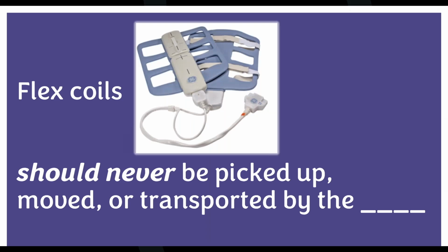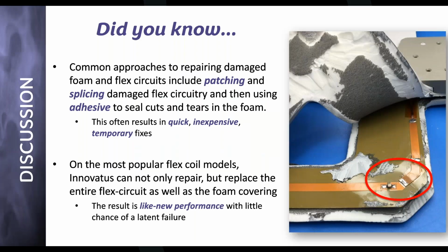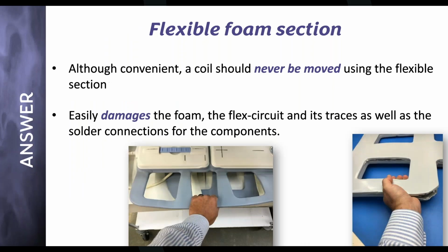Flex coils should never be picked up or moved by the... Anybody else? Patient. Well, no, you shouldn't be picking up your patients anyway, unless you're really strong. So, no, they should never be picked up by the foam section. Even though they're convenient and there seem to be nice handholds on them. Yeah, it looks like a handle. It is not. Inside there are traces, and those are elements, and they are part of the function of the coil, and they can be fragile. So regular use picking them up will ultimately cause the coil to fail.